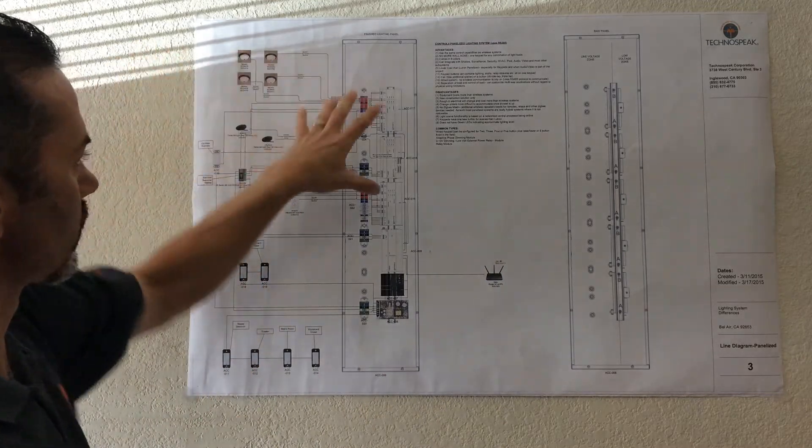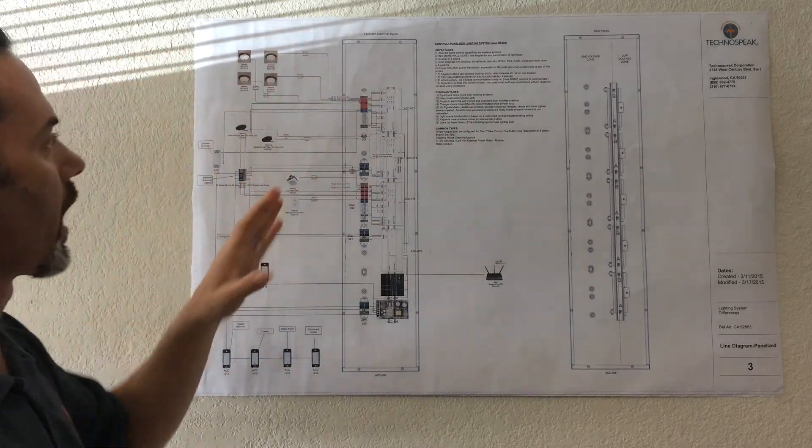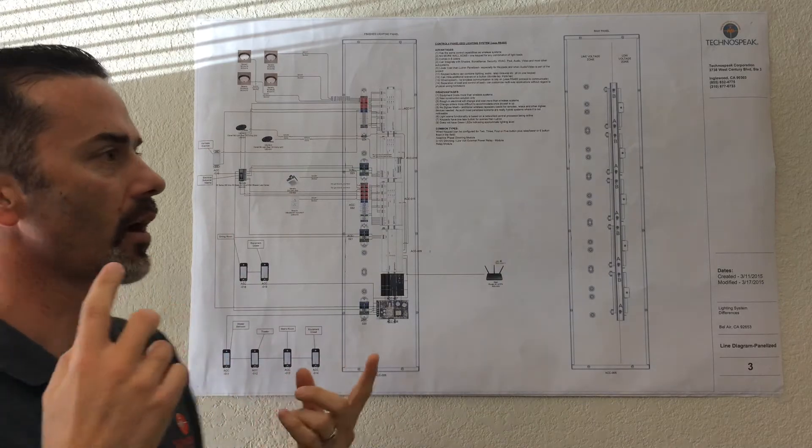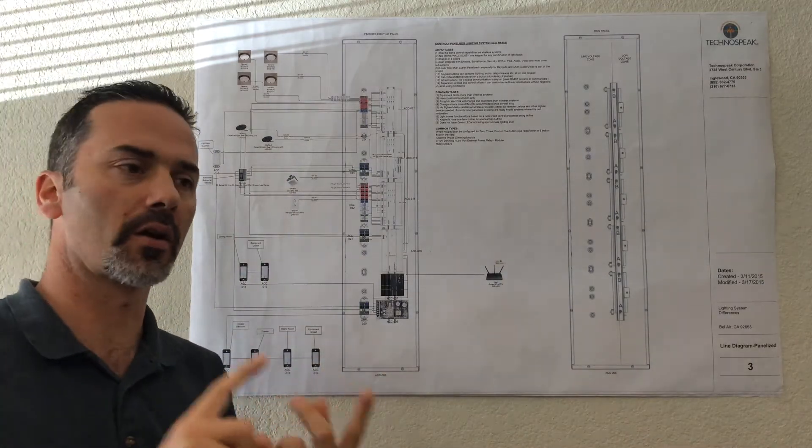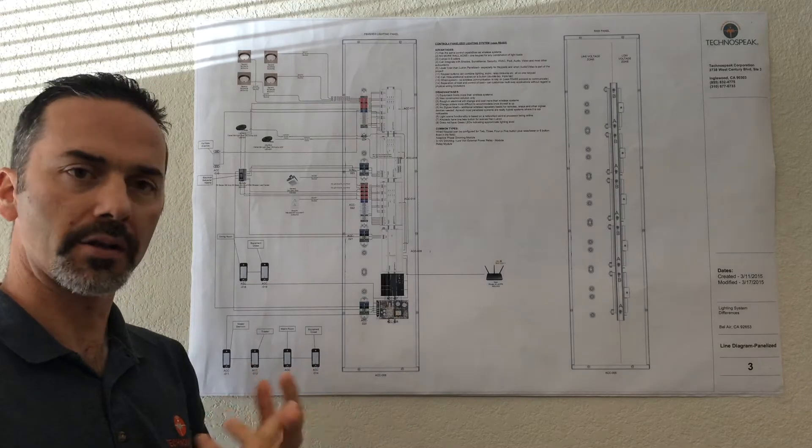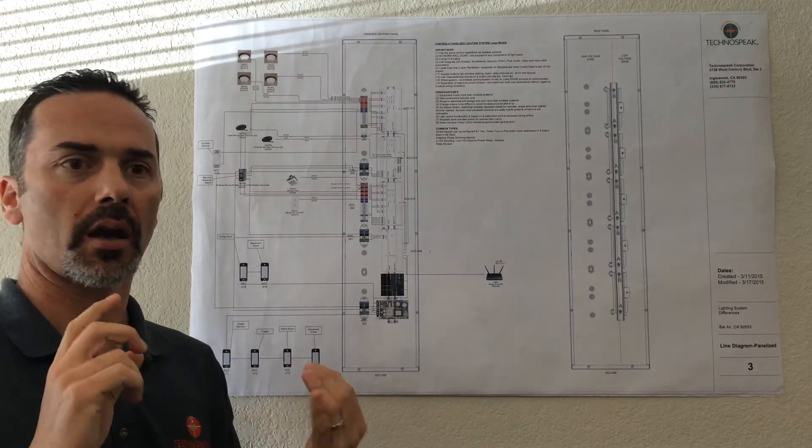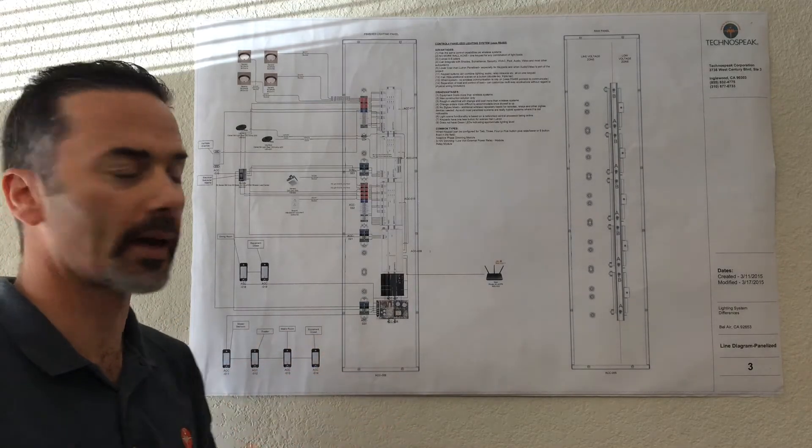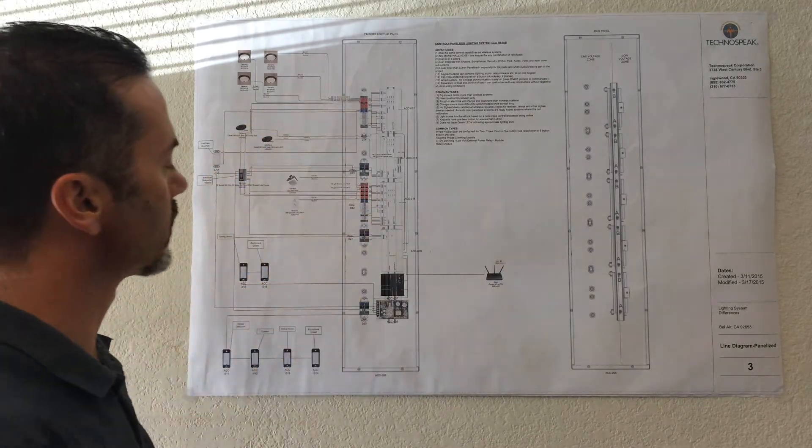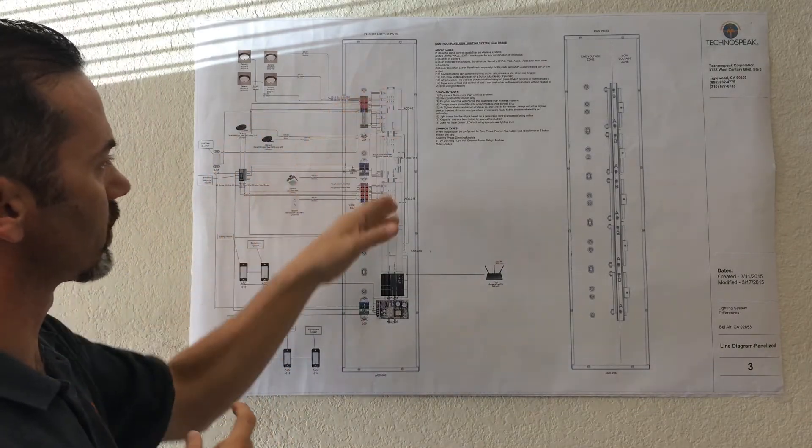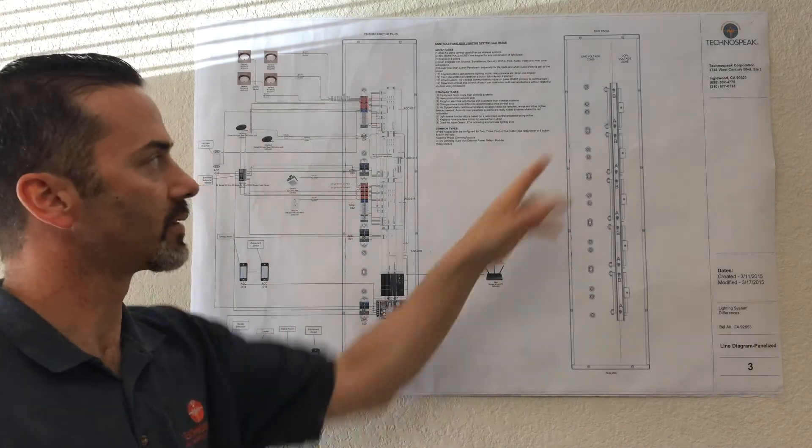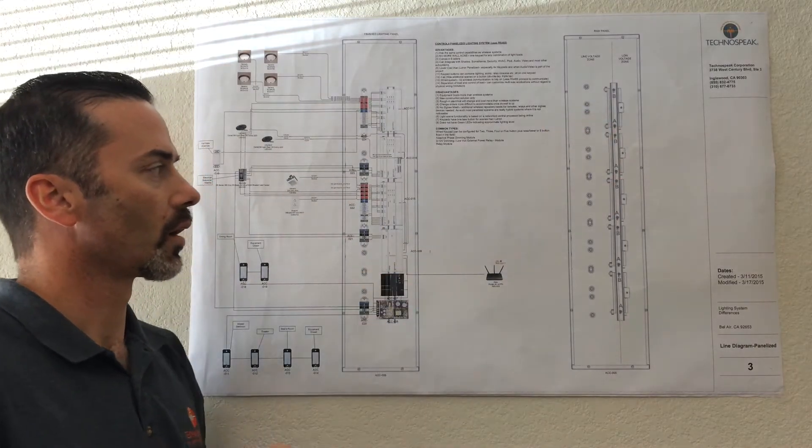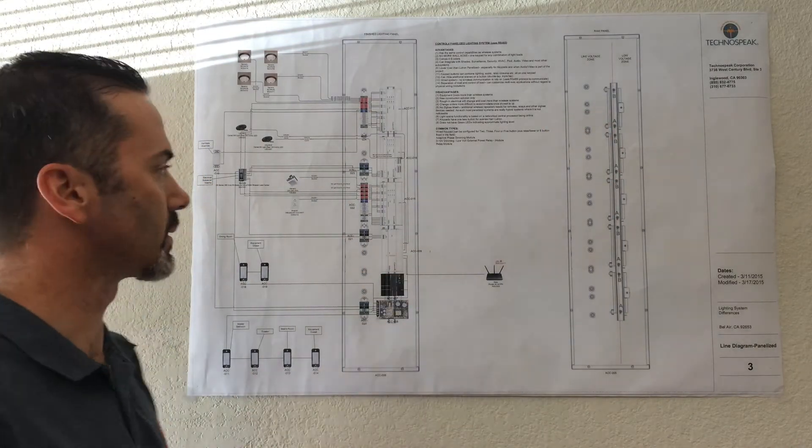Once all the loads are brought in, then we figure out how many and what types of loads we have, how many incandescent loads do we have, halogen loads, LED loads, fans, fountains, pumps, and all that kind of stuff. And then we use different lighting modules that sit on these DIN rails to control all the various different devices.